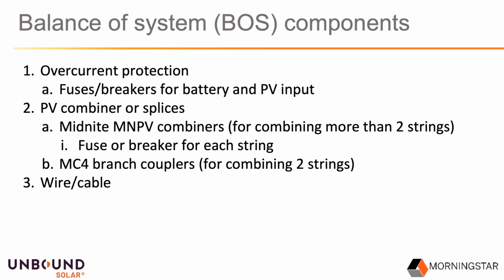There are some related parts that are going to go with the charge controller. Overcurrent protection is something that's necessary for safety and usually for code too, and it's not included in the controllers, either fuses or breakers, and I'll show a diagram on the next slide of that. You're also going to need a PV combiner or splices in most cases, unless it's a very small system. We recommend Midnite has a full line of MNPV combiners in really any size and configuration you want. If it's more than 2 strings, you need a combiner with a fuse or breaker on each string.